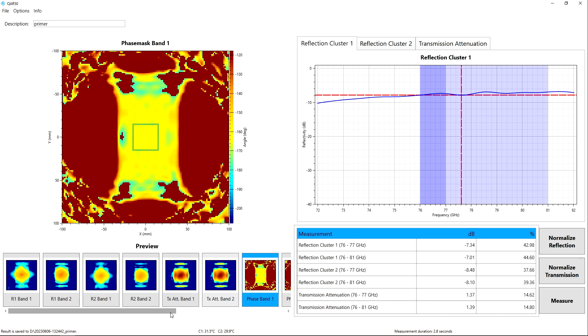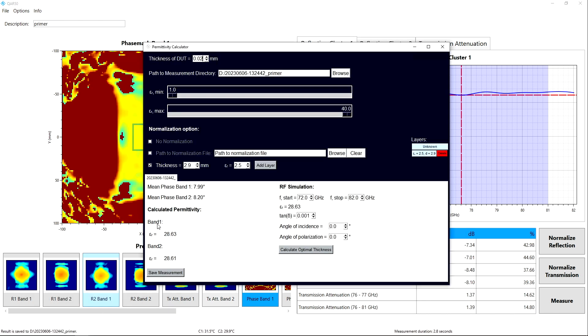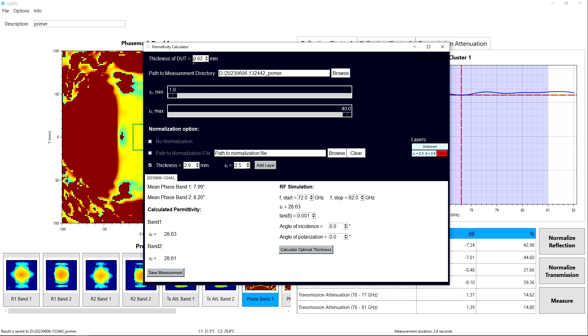The measurement of the primer currently shown in the instrument is the measurement visible on the screen. We are measuring a certain transmission phase, and with that phase and the normalized transmission phase from the previous measurement, we can use the permittivity calculator to calculate the permittivity. The calculator is shown here and can be run on the device. You obviously need to enter the thickness of the layer you want to characterize — in this example, the primer layer is 20 micrometers thick.